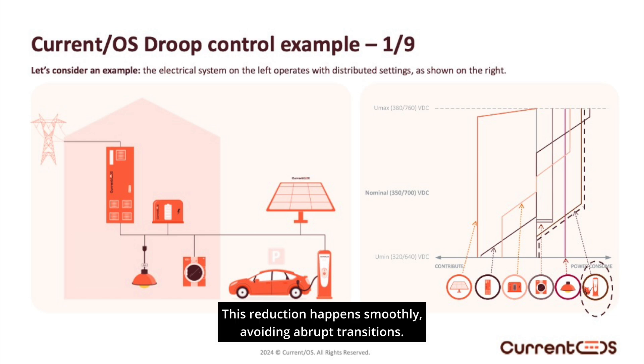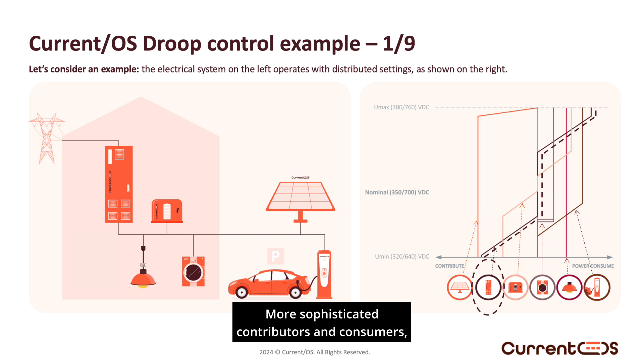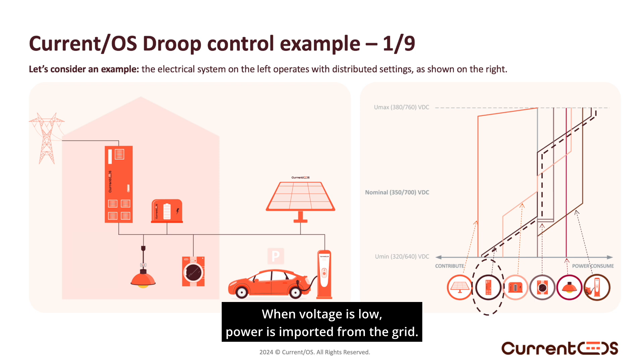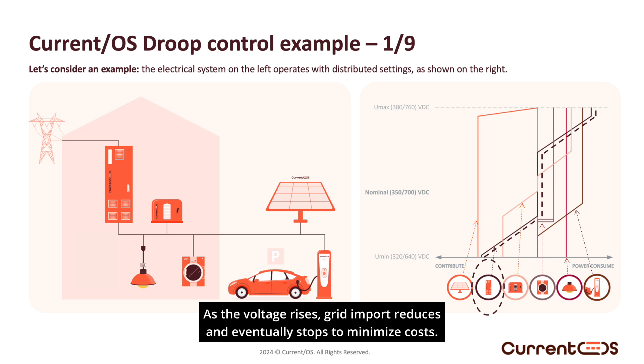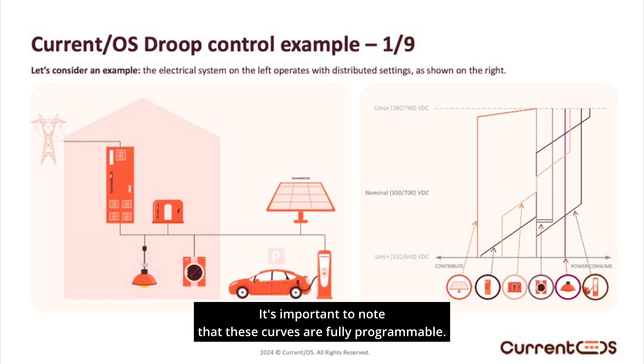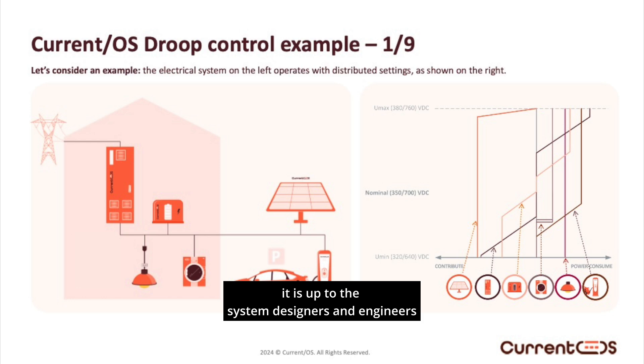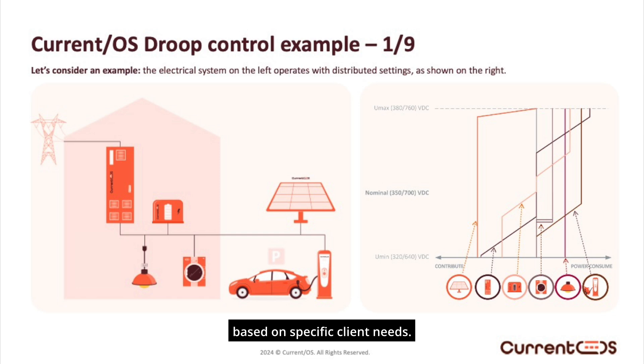This reduction happens smoothly, avoiding abrupt transitions. More sophisticated contributors and consumers, like the public grid connection, operate differently. When voltage is low, power is imported from the grid. As the voltage rises, grid import reduces and eventually stops to minimize costs. If the voltage continues to rise due to excess power, the system begins exporting energy to the grid. It's important to note that these curves are fully programmable — this is just an example. For each project or installation, it is up to the system designers and engineers to define these thresholds based on specific client needs.